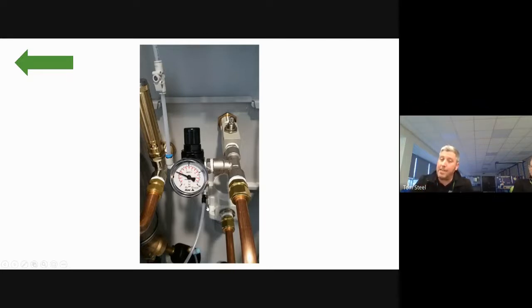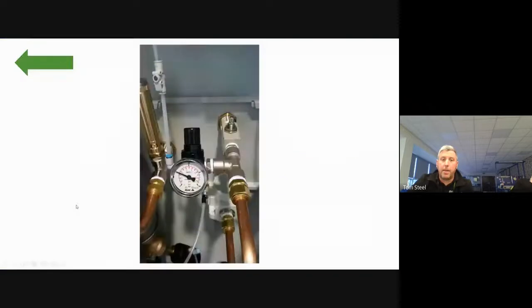The factory settings are there to ensure you have a steady, constant purity and flow of oxygen. If you affect these and you increase the flow output, then you will affect the purity. It directly affects the purity, okay? So that's something just to keep in mind. We're going to check basically what I've just already said, the output flow controller and the pressure regulator. We've also got a small portion we take off, and that's for the oxygen analyzer itself, okay? So we don't want to adjust that. It's adjusted in the factory. If you start messing about with any of the settings, it will affect the purity. And that's the most important thing to remember.